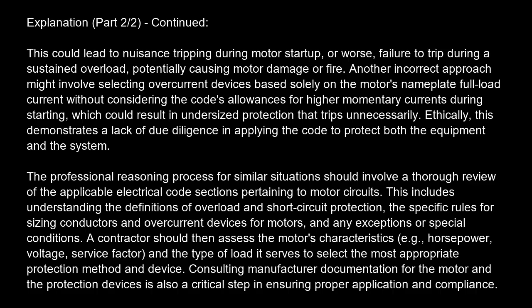The professional reasoning process for similar situations should involve a thorough review of the applicable electrical code sections pertaining to motor circuits. This includes understanding the definitions of overload and short-circuit protection, the specific rules for sizing conductors and overcurrent devices for motors, and any exceptions or special conditions. A contractor should then assess the motor's characteristics, e.g., horsepower, voltage, service factor, and the type of load it serves to select the most appropriate protection method and device. Consulting manufacturer documentation for the motor and the protection devices is also a critical step in ensuring proper application and compliance.